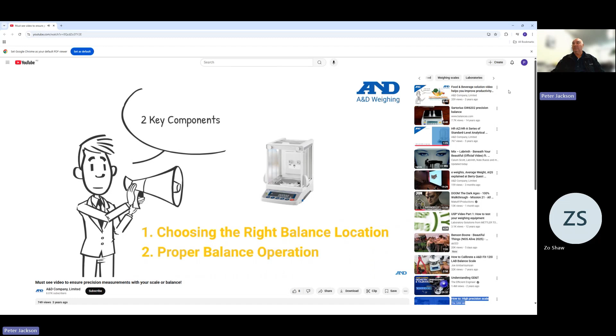Secondly, the surface on which the balance is placed must be very stable and free of any vibration. Third, balance placement in the room should be such that it minimizes sunlight and air currents. Fourth, environmental conditions such as temperature fluctuation and relative humidity need to be considered as well. The room should be vibration-free, with no drafts or electrostatic charges, and maintain a constant temperature. Weighing results vary widely when exposed to significant changes in room temperature. Be sure to stay away from windows and refrigerators.